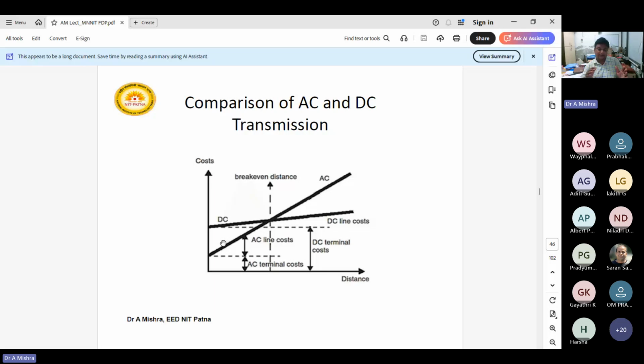Why at the lower distance is it cheaper, considering operational cost? If you are going for the longer distance, operational cost will be a different issue. But equipment cost means the terminal equipment you are using, and line cost means the number of conductors and towers you are using. So that is less in AC if the distance is less, because these are the conventional things that have been used for a long time.